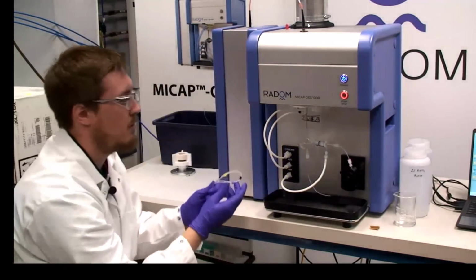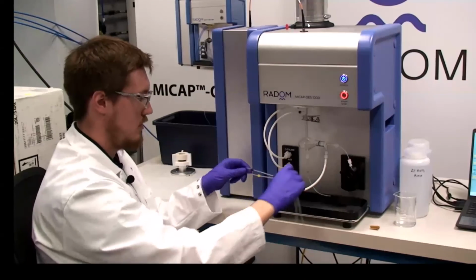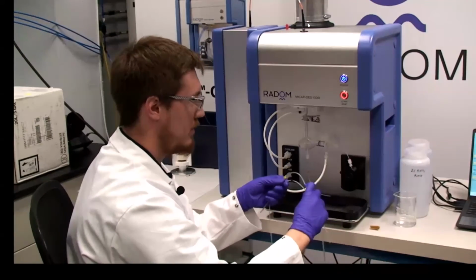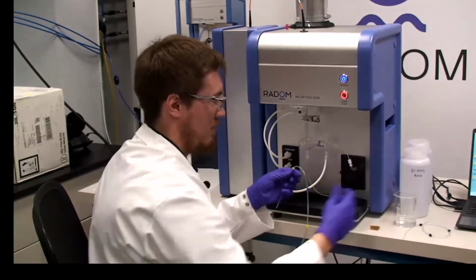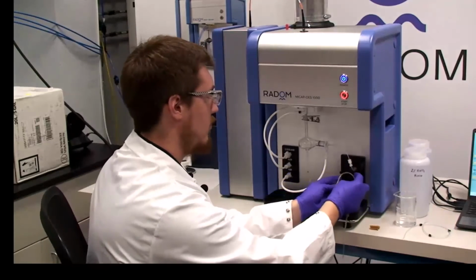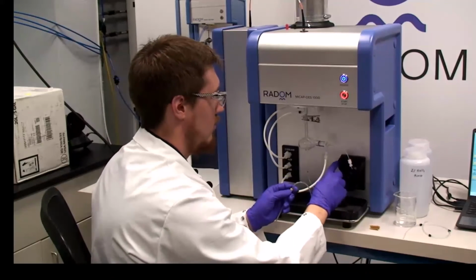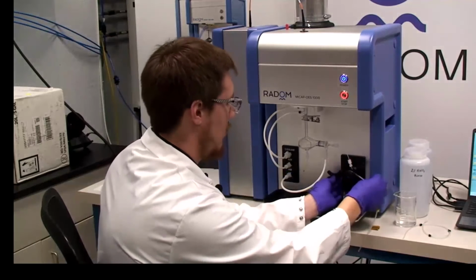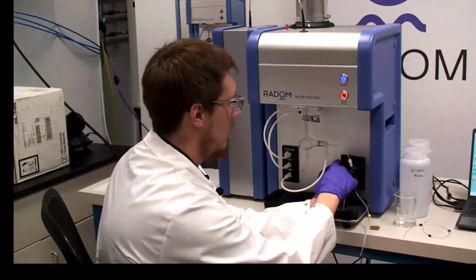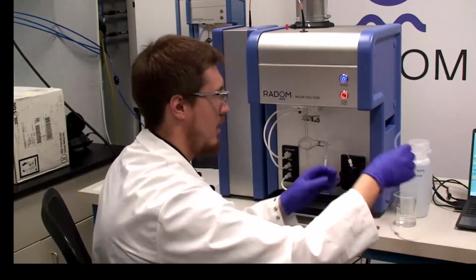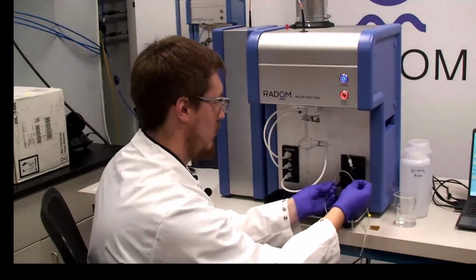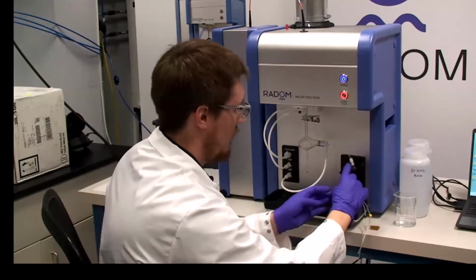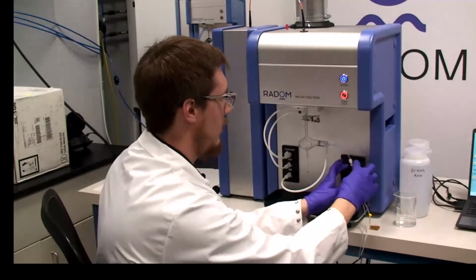Finally, we have our pump tubing and our peristaltic pump. Depending on the speed of your pump and the size of your pump tubing, that will determine the amount of volume that goes into the nebulizer. So I would start with the farthest back line that you're going to assemble, which is our waste line. Clip both sides in. And then our sample line, which I'm putting in the front here. So those get clipped in on both sides and then clamped down on the top.